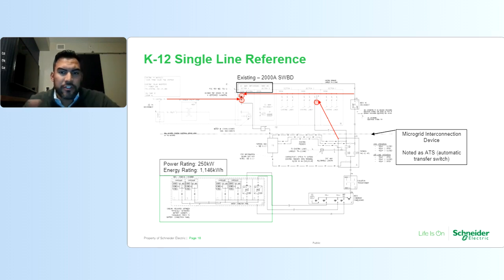So here, we actually took this interconnection device and replaced it with SourcePack. SourcePack was the point of interconnection between the main switchboard and the energy storage system. And this client had already separated their essential loads. Again, this was great for an existing facility, right? If you're an existing facility that has space on your main switchboard, a spare breaker, SourcePack can be that point of interconnection between that main switchboard and your critical loads, adding on an energy storage system and/or PV system to your facility, getting those grid connected benefits and also the resiliency.